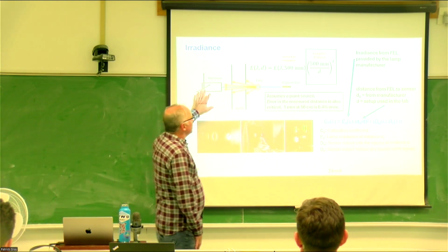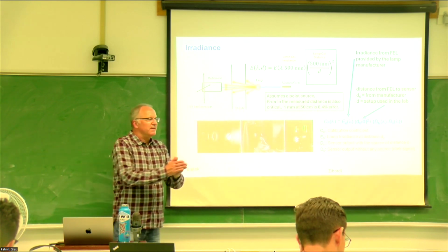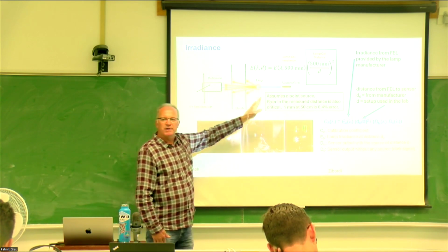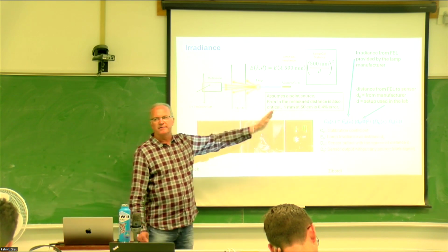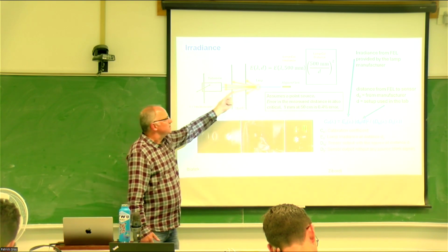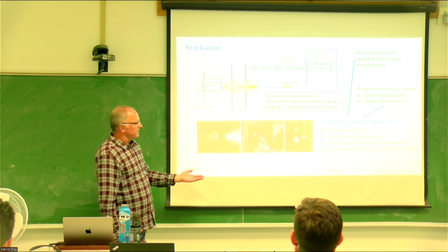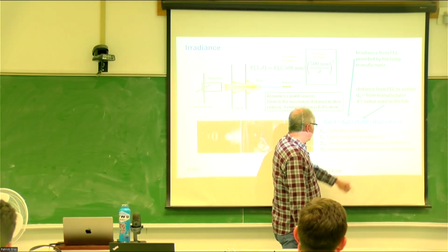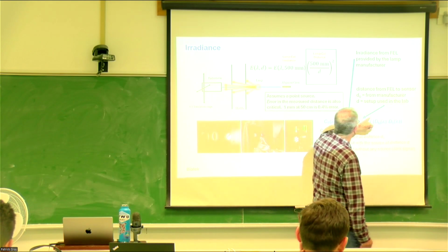Now, depending on what type of sensor you have, you may need to move the distance back and forth to bring it in range, so you're not always measuring saturation of the sensor or not having enough light. So this distance can change and it's variable. You correct for that distance. There's a factor in here: it is the distance from the FEL to the sensor.